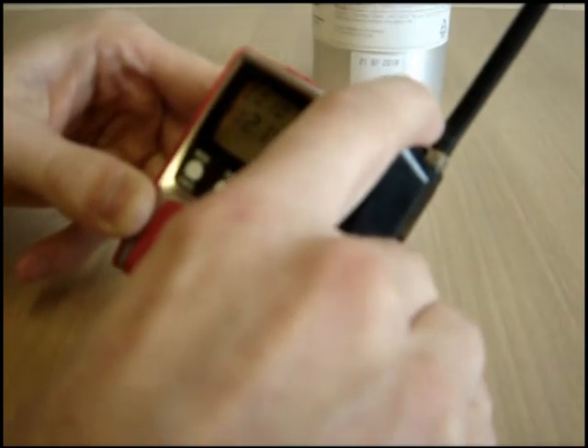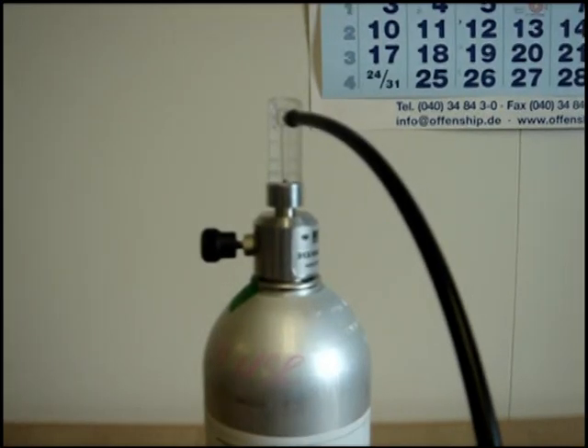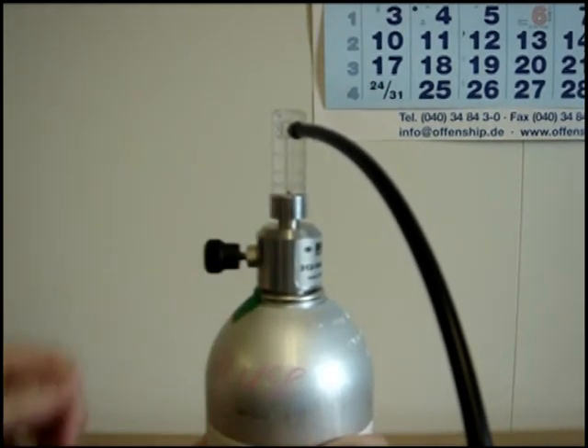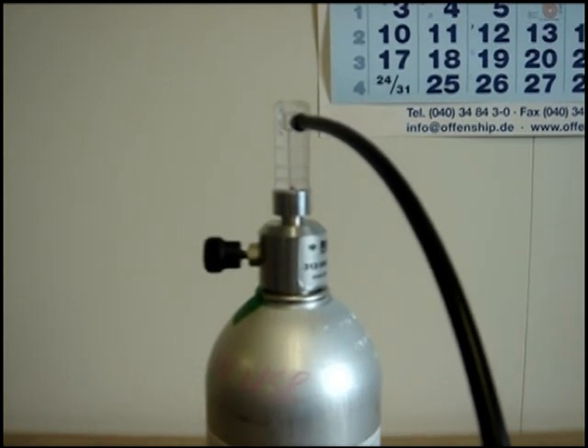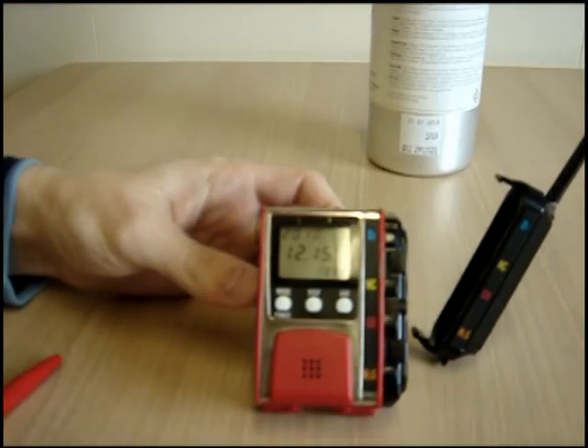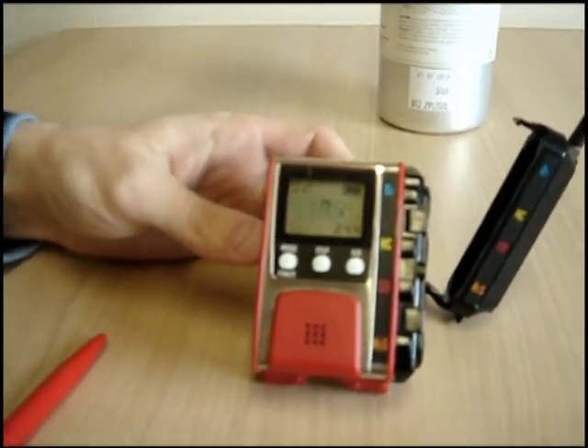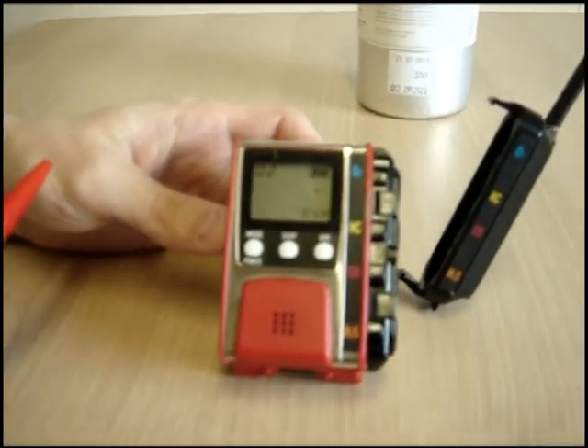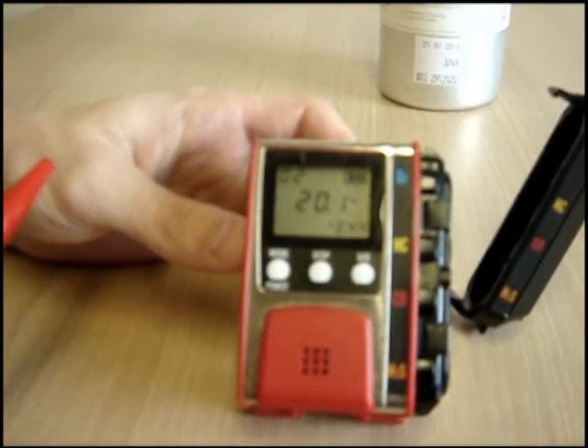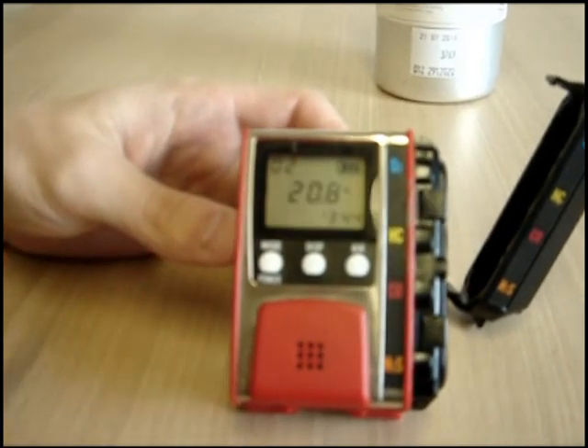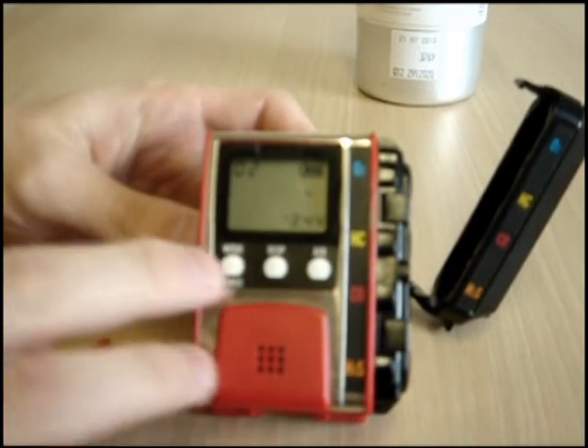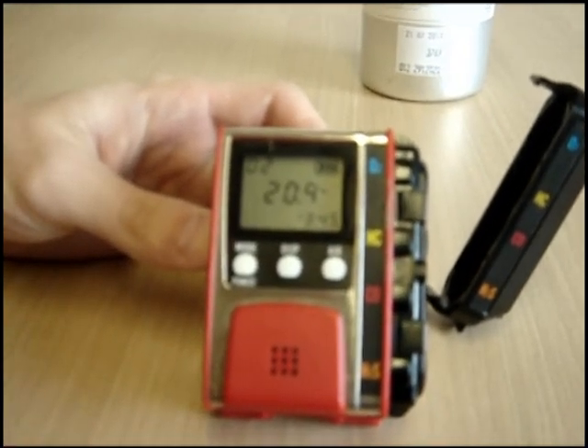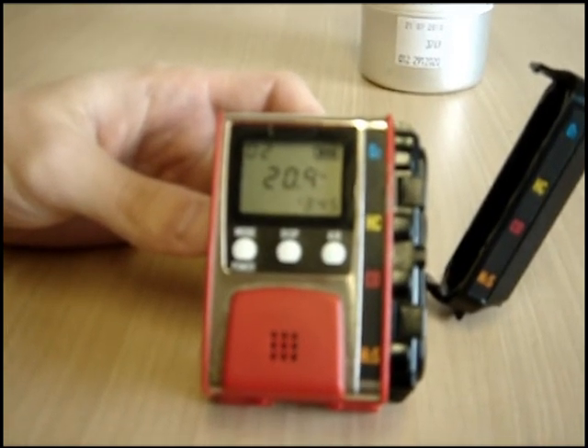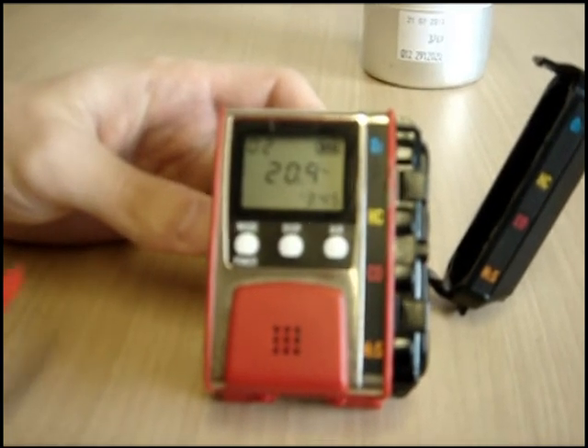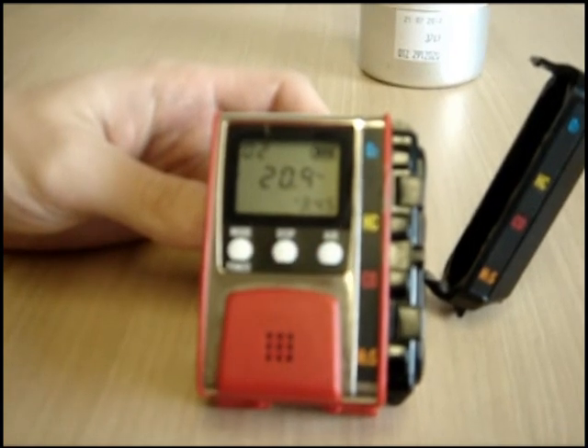So finally, we push the power button and we remove the flow device from the equipment, and close the valve on the flow meter so as not to consume the span gas anymore. It will give you the alarm because it's still full of gas. When you have a proper reading of oxygen and the other gases, you can push the power button to shut down the alarm. Now the device is calibrated with the span gas, and the only thing remaining before each use is to make the zero calibration in fresh air.